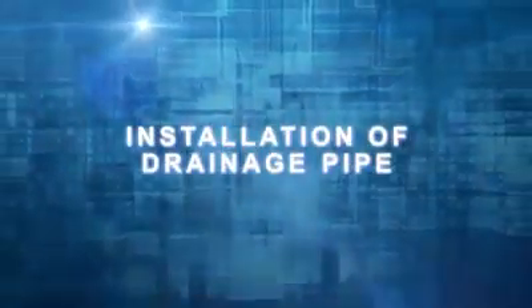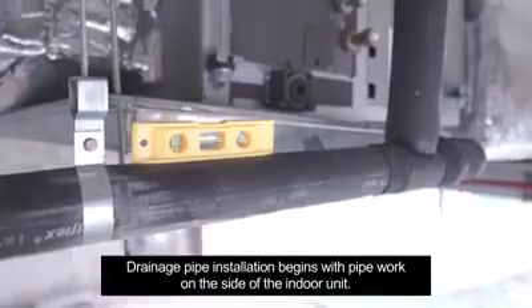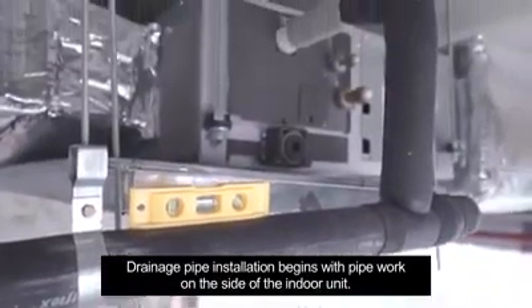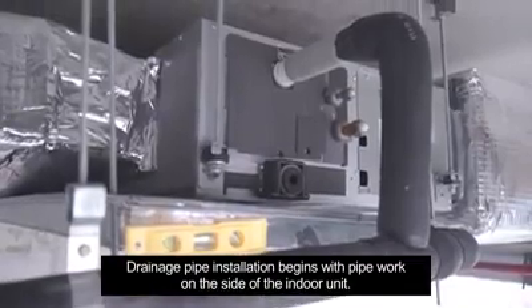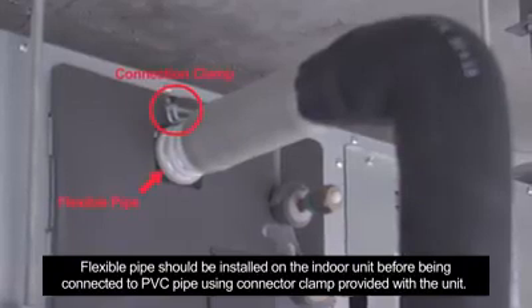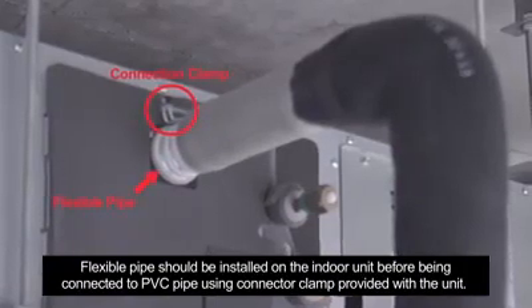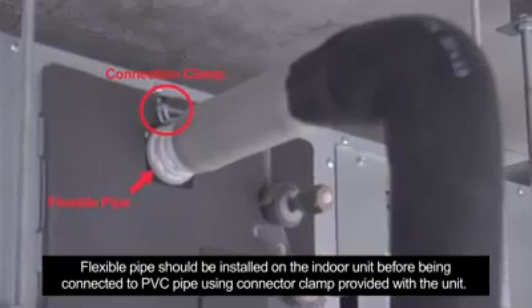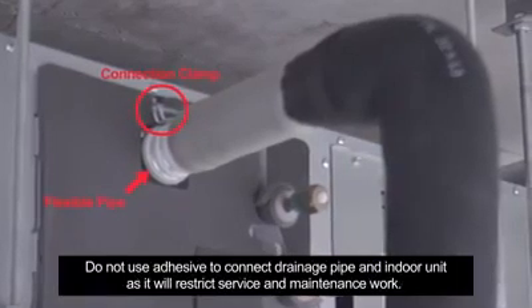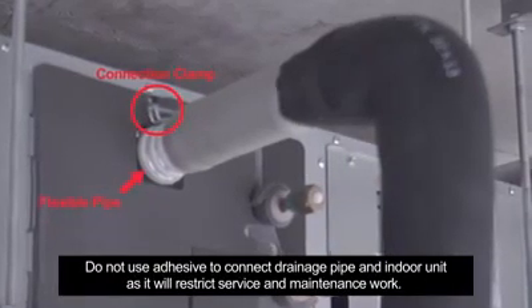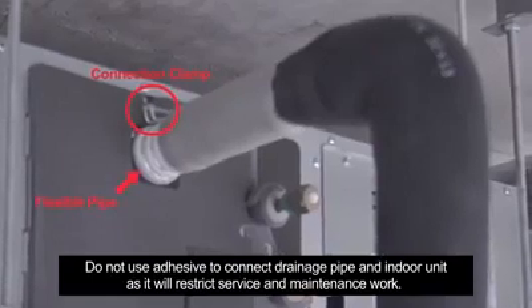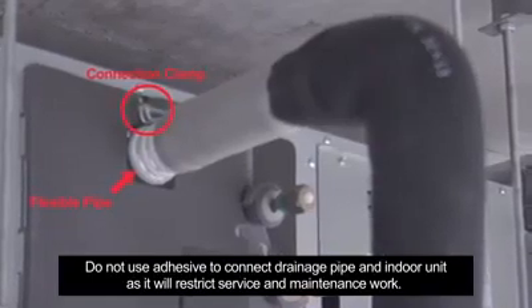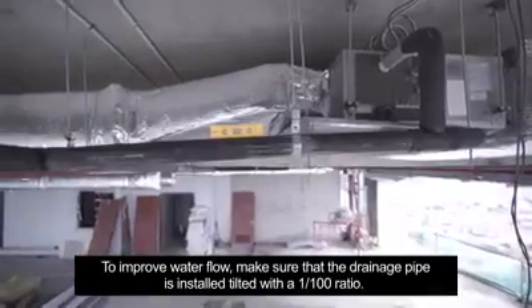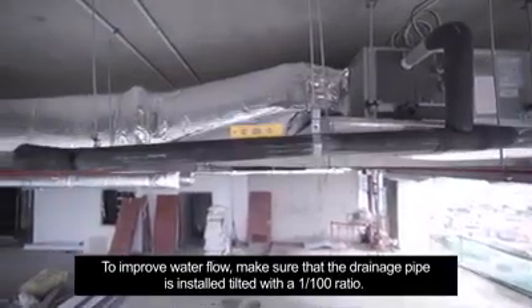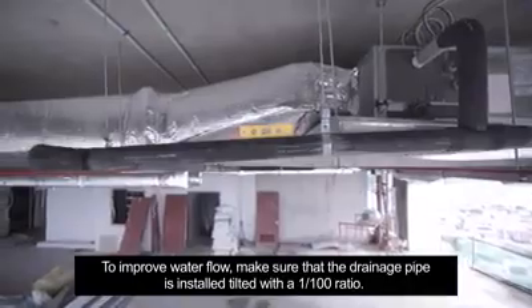Installation of drainage pipe. Drainage pipe installation begins with pipe work on the side of the indoor unit. Flexible pipe should be installed on the indoor unit before being connected to PVC pipe using connector clamp provided with the unit. Do not use adhesive to connect drainage pipe and indoor unit as it will restrict service and maintenance work. To improve water flow, make sure that the drainage pipe is installed tilted with a 1:100 ratio.